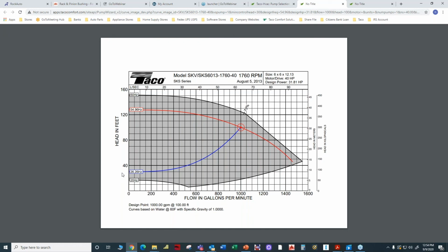Now I have another curve where the control head is at 30 feet. Did I do that correctly? Yes. It's 10, 20, 30, yes. And 150 gallons per minute. So now I'm much closer to the actual pressure drop at minimum flow.